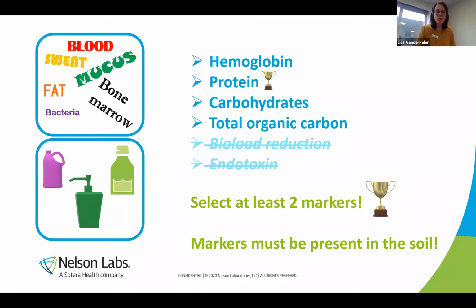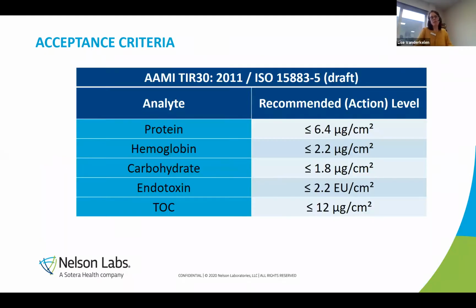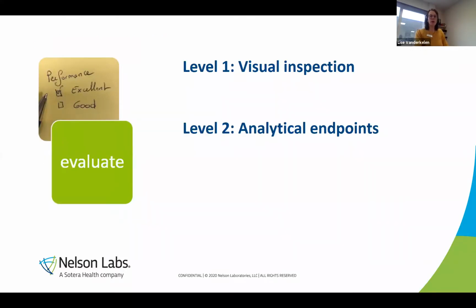What are the acceptance criteria? The acceptance criteria can be found in TIR30 and in the new draft of ISO 15883. And it is described in this table. So for proteins, it has to be below or equal to 6.4 micrograms per square centimeter. If it's below that, you have a pass. If it's above that, if it's 6.5, you have a clear fail. It's a fail of your cleaning evaluation. So we have already 2 levels.